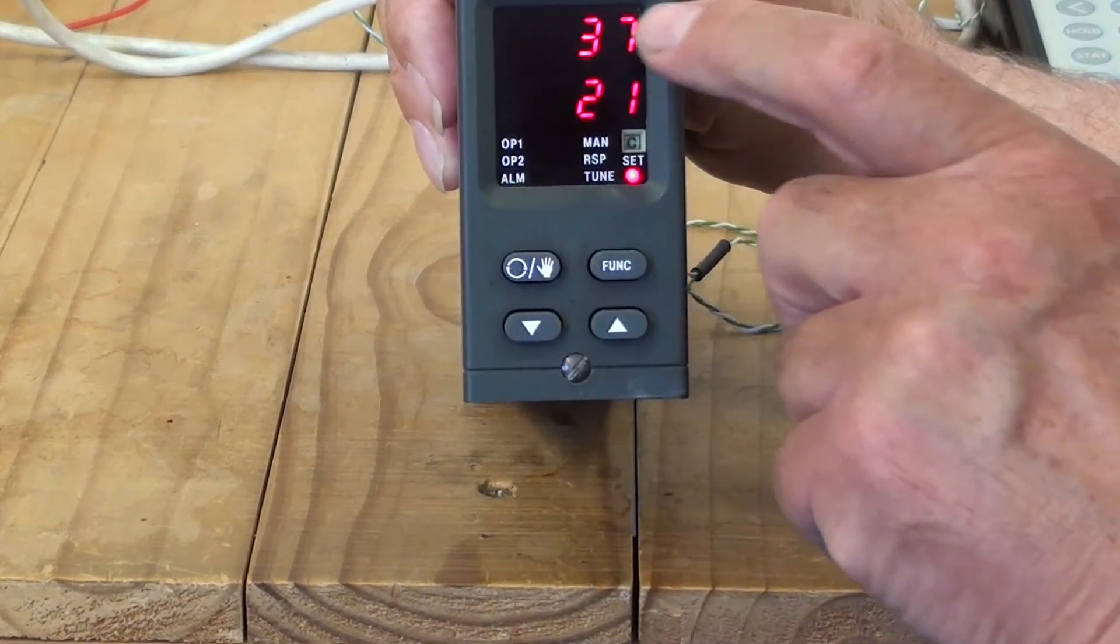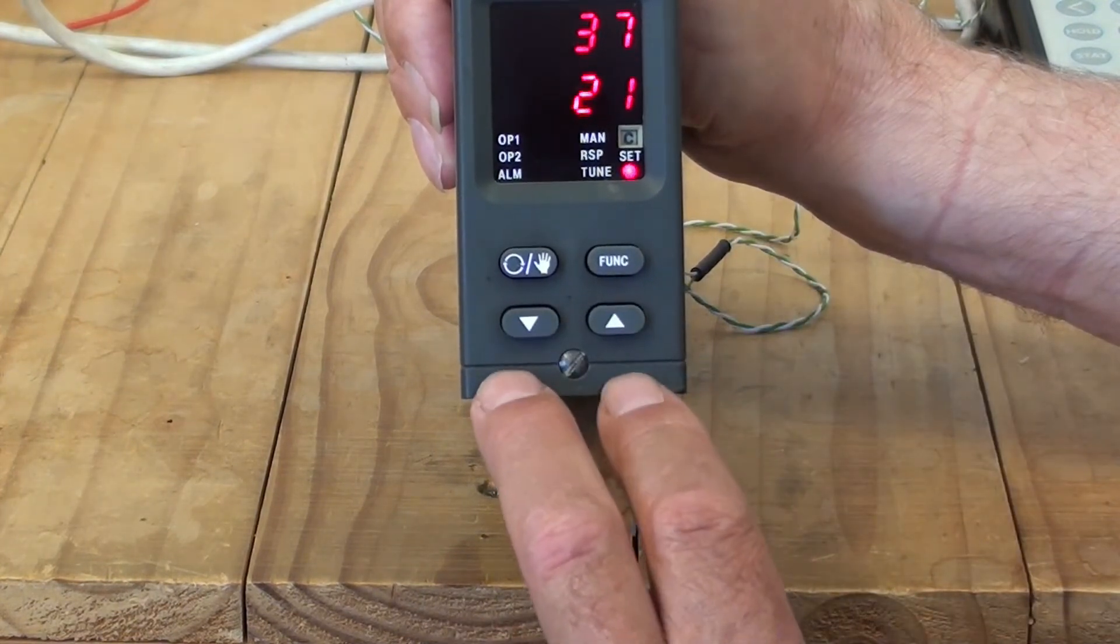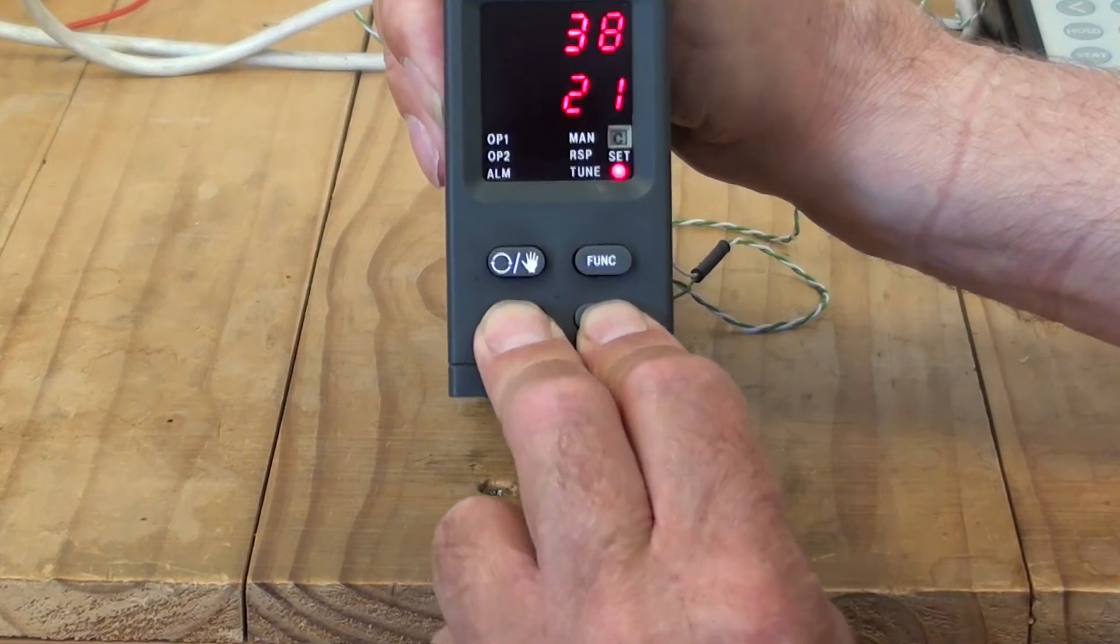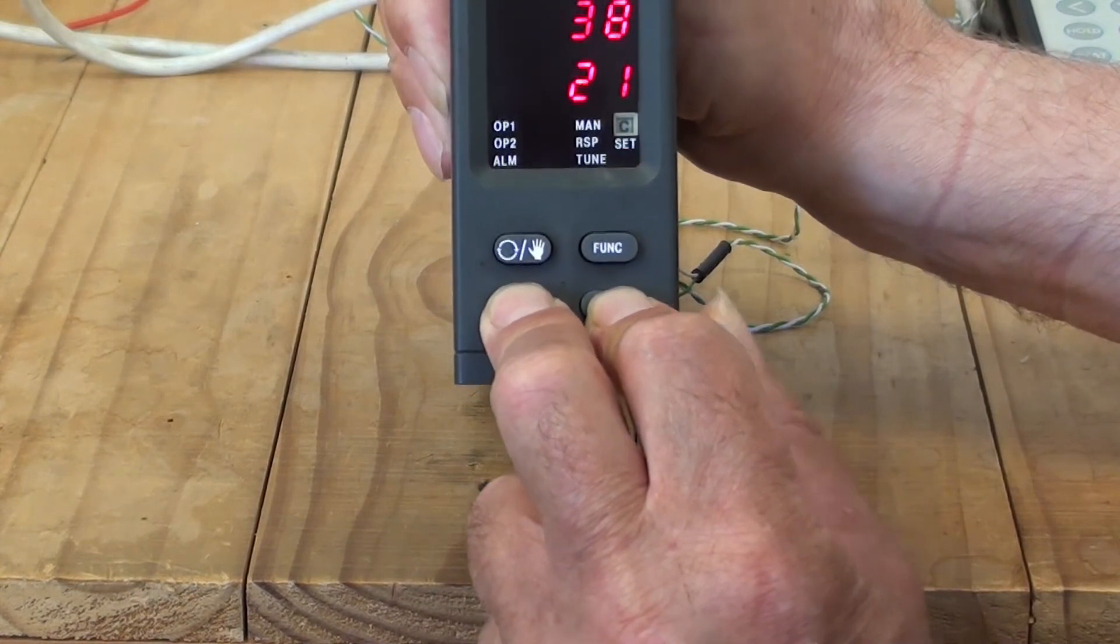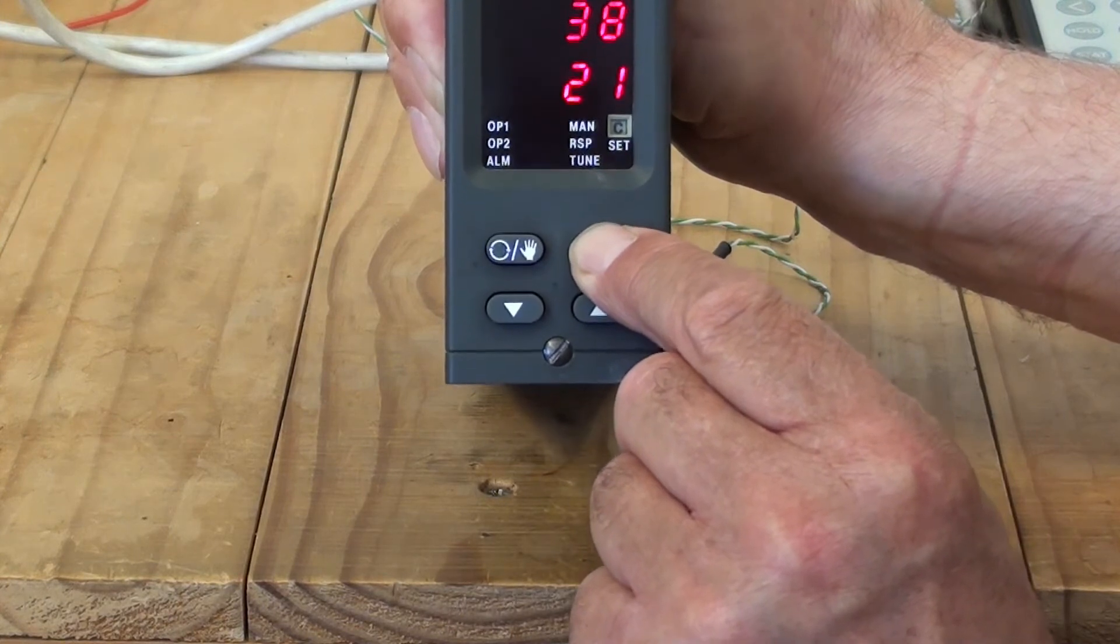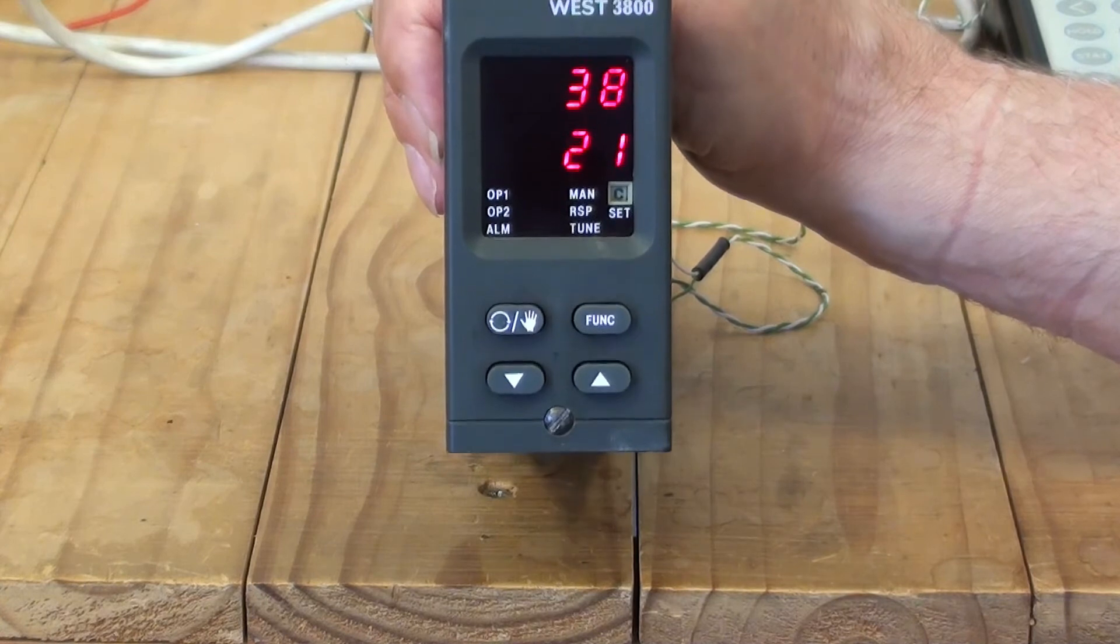Come back to the process value at the top, the setpoint on the bottom, and press the up and down arrows together, the raise and lower arrows together. Hold them for five seconds. Display flashes. Set light flashes. Press function key for about three seconds until it goes off. Now you're back into normal operation mode again.